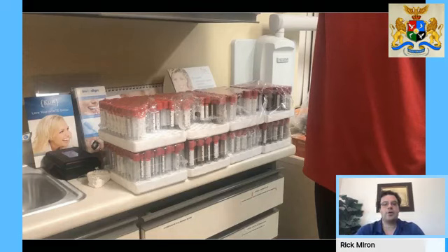In this video here, I want to show you some of the research that we've done over the years because this is 8 different types of tubes. Okay, they're all red top. They all look very similar. There's little differences here. So you can see this glass is a little darker than this one. But the bottom line is in these studies, we're testing different hydrophilicity of different tubes. So we're doing different chemical treatments of the tubes, different processing techniques, different mixtures of glass. You can do many different things to try and create a more hydrophilic tube surface.